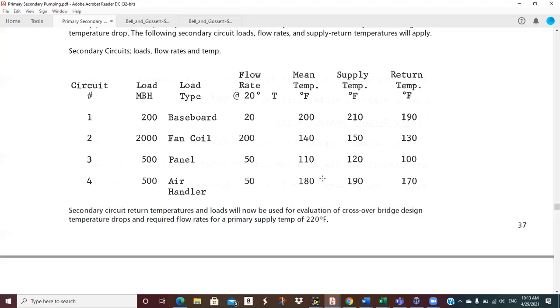Then I've got some panel heating equipment, and it's 500,000 BTUs an hour. So that's going to require 50 GPM at a 20-degree delta T. I'm speccing that at 120 in, 100 out, and 110 mean temperature. Then for my air handling, I've got some big air handlers. That's going to be 500,000 BTUs an hour, so I need 50 GPM for those, at 190 in and 170 out. And I have selected my primary supply temperature at 220.